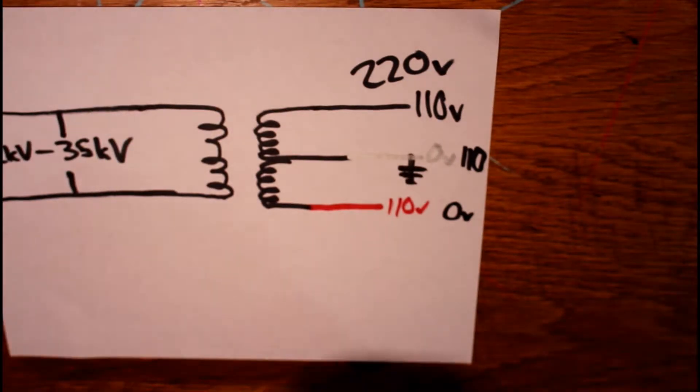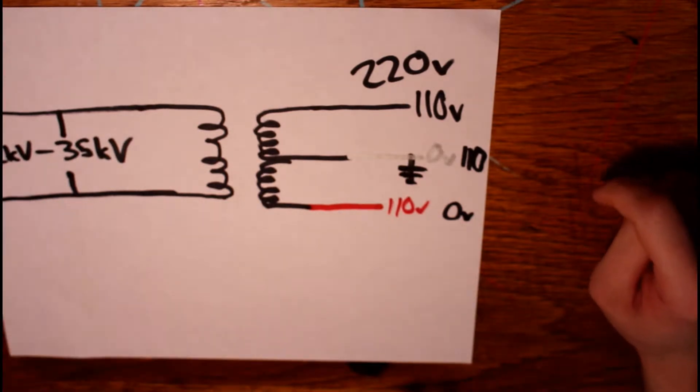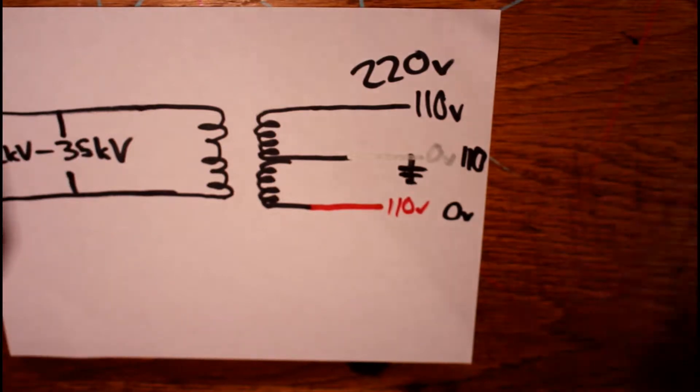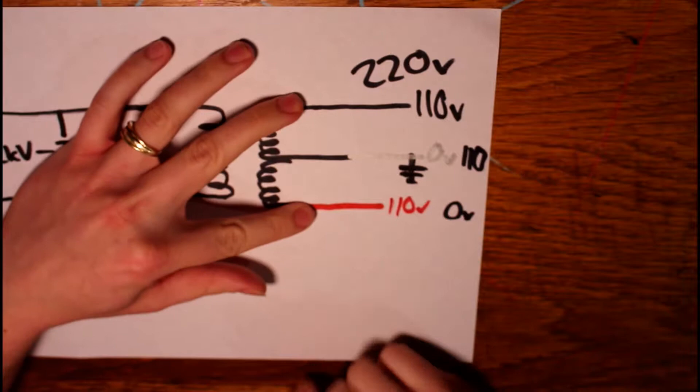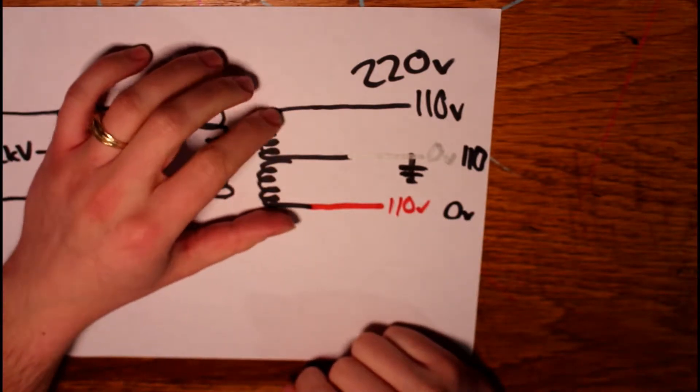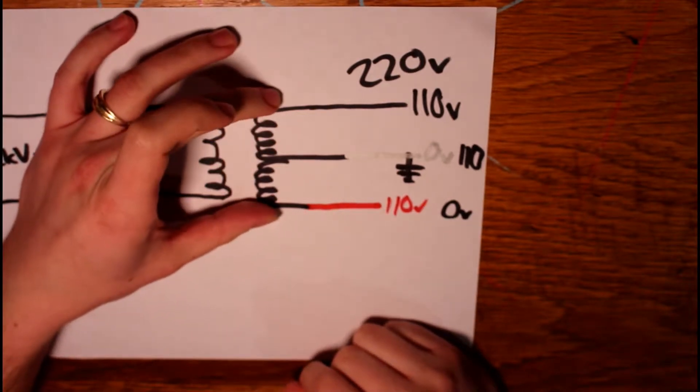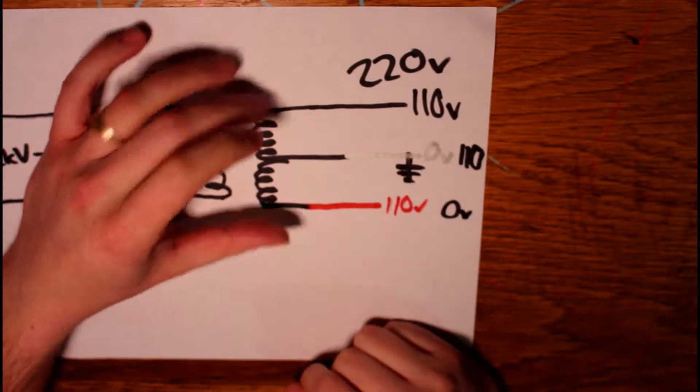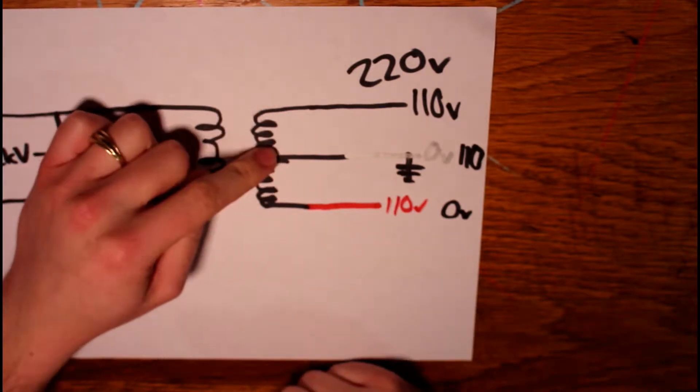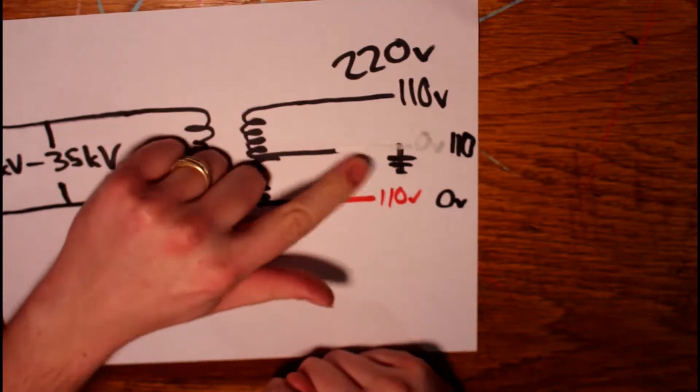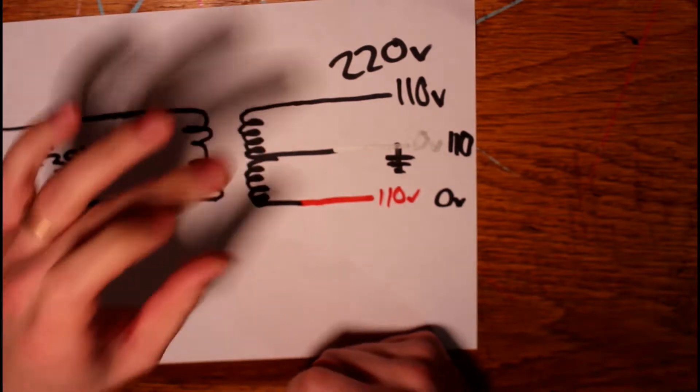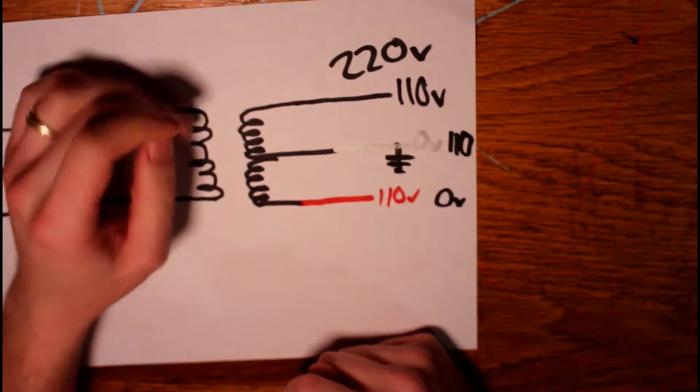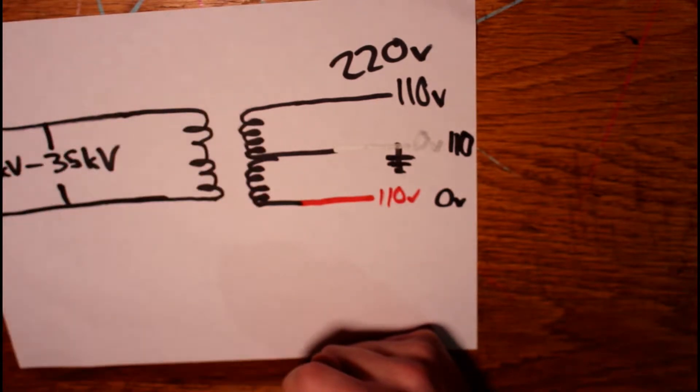The important takeaway there is that there's not a separate 110 volt line and a 220 volt line coming to the house or going through the house. There's just these two outer legs of the secondary of your distribution transformer. There's a 220 volt RMS difference between these two legs. And then there's the third leg, a center tap, that's half the voltage between these two. That has a connection to ground at various places. So we call this zero volts, and we call these outer two 110. The outer two together, though, 220 volts between them.